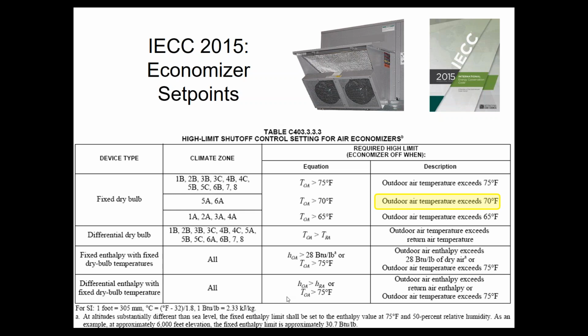If I have an enthalpy economizer, I need to set it for 28 BTUs per pound of dry air. No one knows what that means, right? Probably not. And 75 degree cutoff. We will show you on a psychrometric chart what that means. And if you have differential enthalpy, then, well, it's pretty straightforward. If the return air is worse than the outside air, take the outside air. So 70 for dry bulb, 75 and 28 for enthalpy.